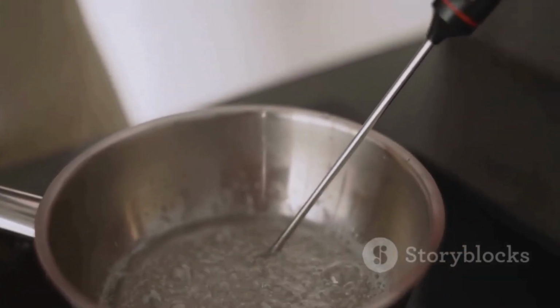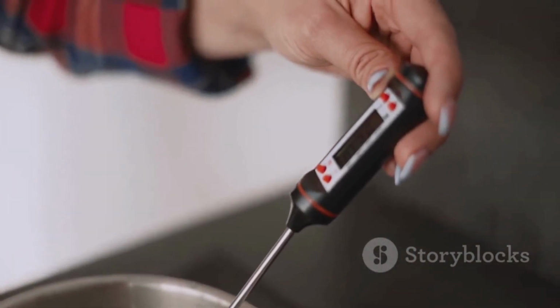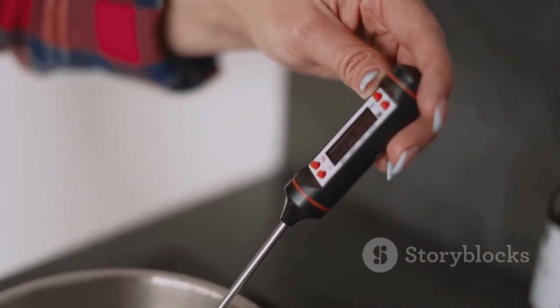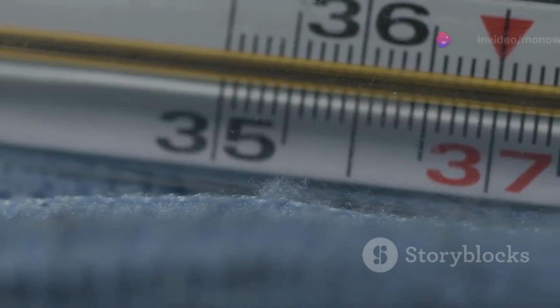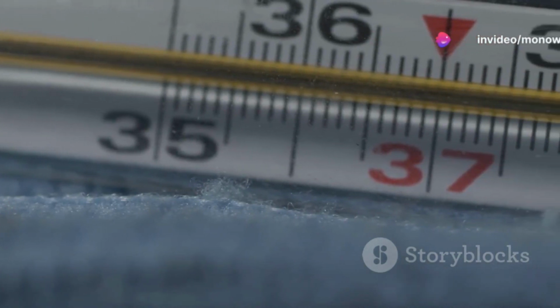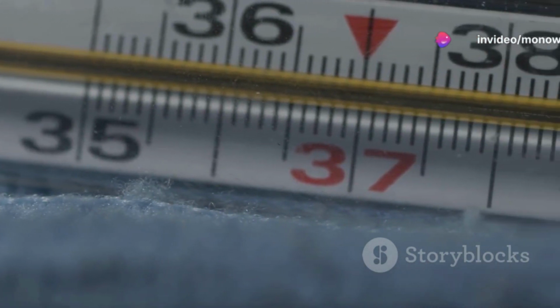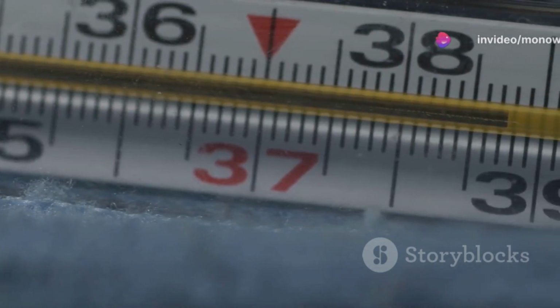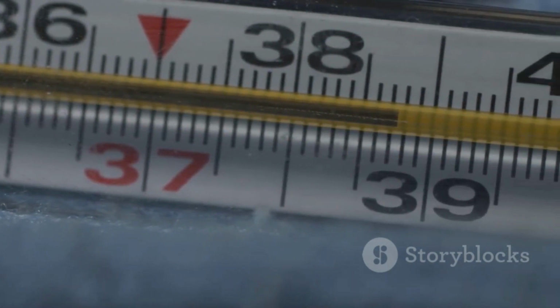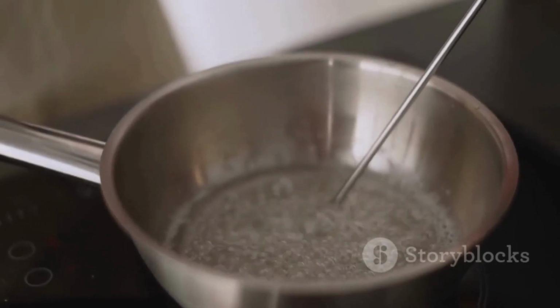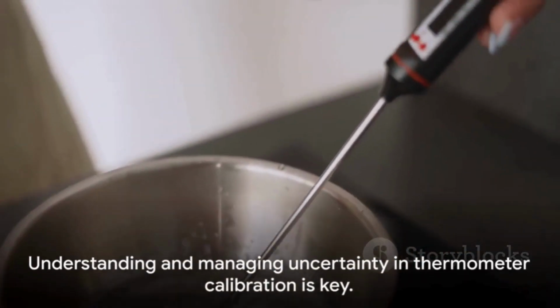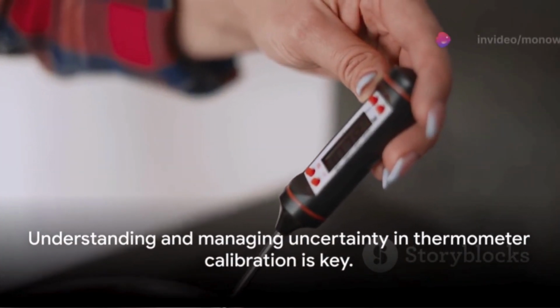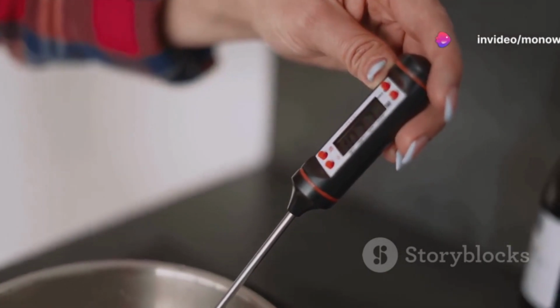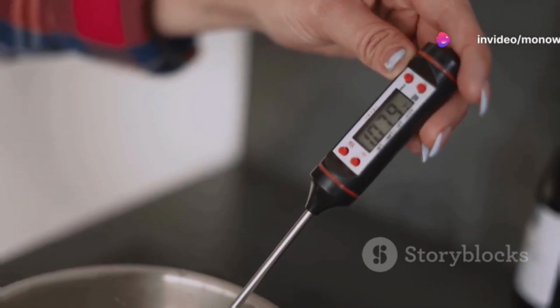We also acknowledged that uncertainties can arise from the material of the thermometer itself. Different materials react differently to temperature changes, thereby influencing the calibration process. Lastly, we looked at how temperature gradients within the medium being measured can contribute to uncertainty. If the temperature isn't uniform throughout, it can lead to inaccurate readings. So, while thermometer calibration is crucial, it's equally important to understand and manage these sources of uncertainty.